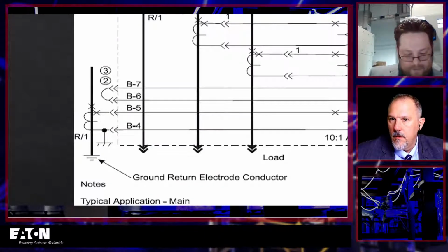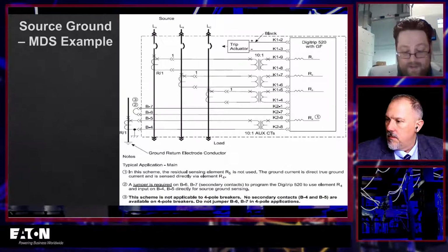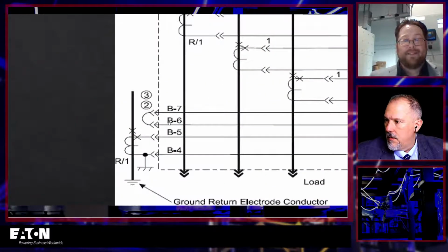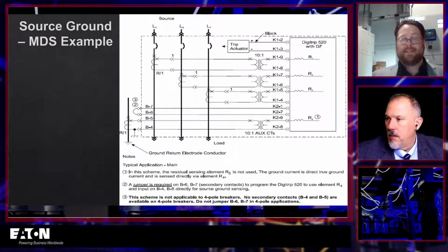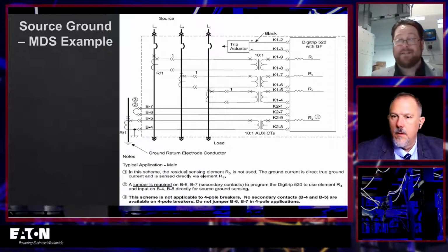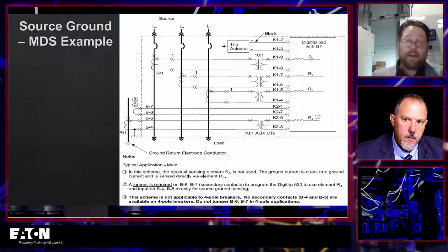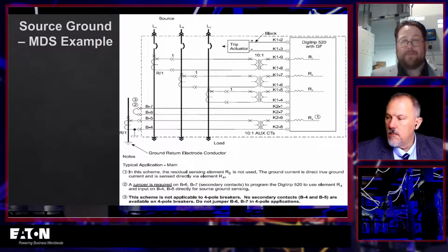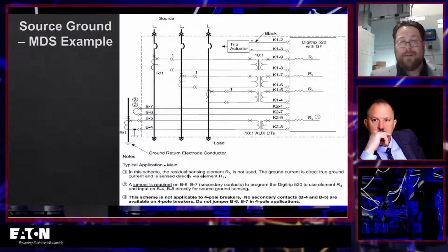Now, I believe, and let me just read my notes here. Yes, in this instance, there's that jumper B7 to B6. That's how the trip unit actually knows that that's how you're measuring ground fault current. So when we talk about testing of the system, it's not just confirming that CT ratio. It's not just confirming that when you inject current through the CT, it goes into the trip unit. You're confirming the settings. In some breaker types, some trip units or relays, there could also be jumpers that need to be installed. And anybody that has looked at these trip units or backup relays knows some of those jumpers are very small.